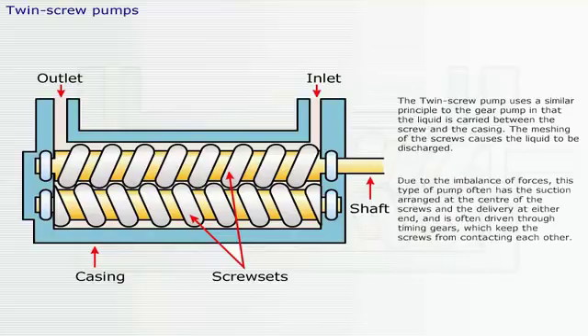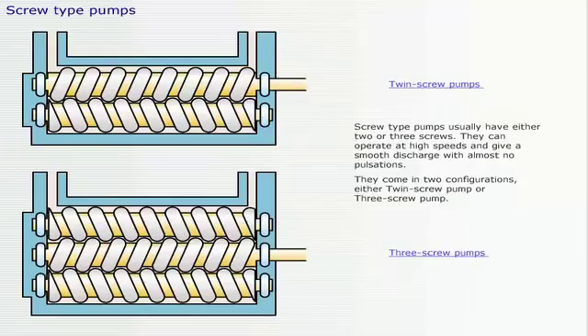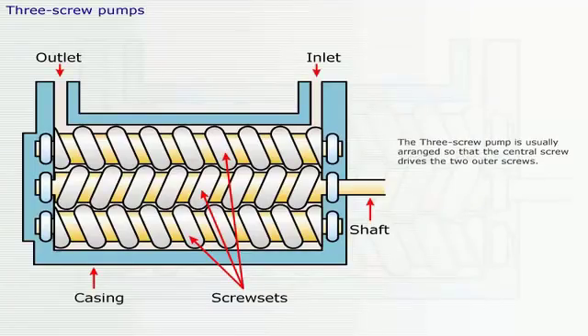Due to the imbalance of forces, this type of pump often has the suction arranged at the center of the screws and the delivery at either end, and is often driven through timing gears, which keep the screws from contacting each other. The three screw pump is usually arranged so that the central screw drives the two outer screws.